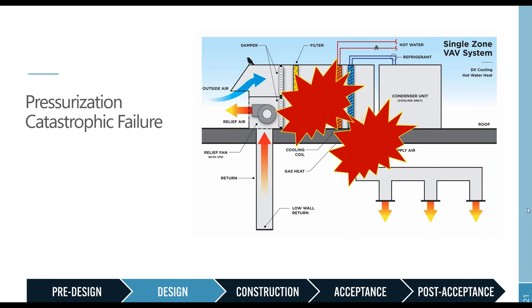This can obviously result in some huge delays during construction and even more major issues for building owners if this happens when the building's occupied. The fix is, of course, pretty easy. It's a pressure safety device which will physically kill the power to the fan if the safe pressure range is exceeded. An additional precaution is to install a sensor to confirm your dampers are open before enabling the fan. However, this can be overridden, so we do always recommend the safety switch.